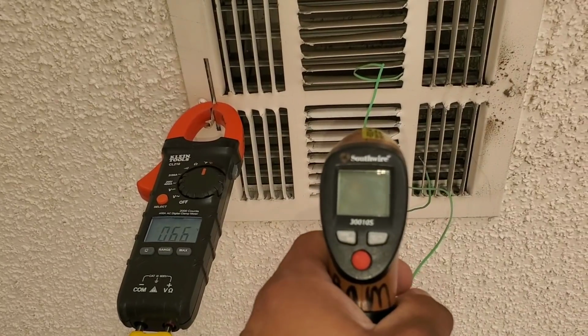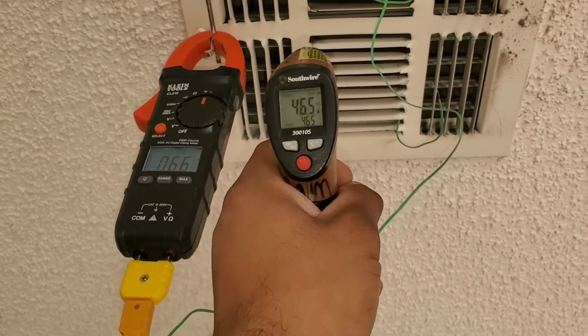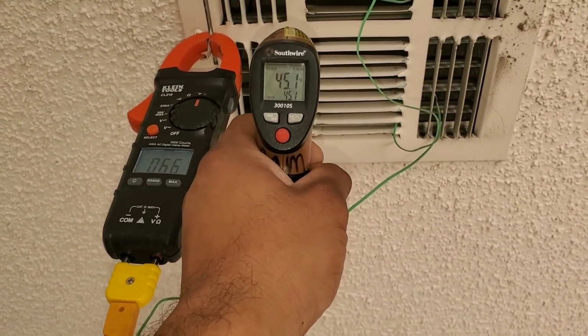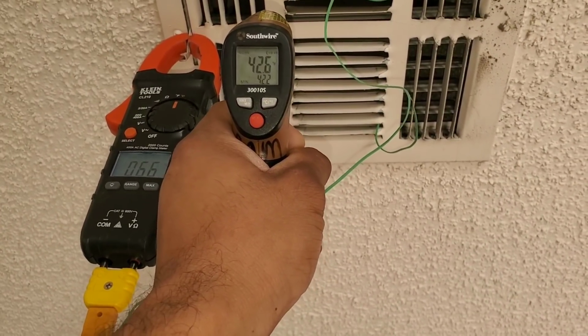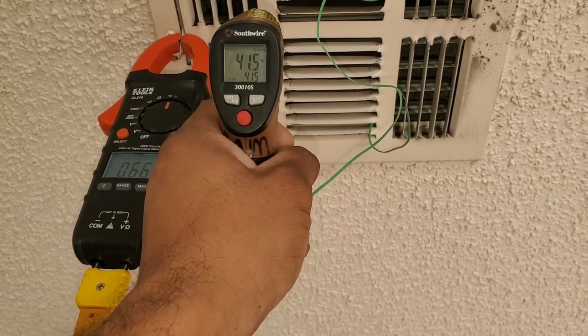I did post a video on my channel explaining the difference between the two, and you can see if I was to look at my temp gun and I'm pointing it at the duct, it's giving me a reading of about 40 degrees. So the proper way to do it is always going to be going off of your multimeter and using your temp probe.